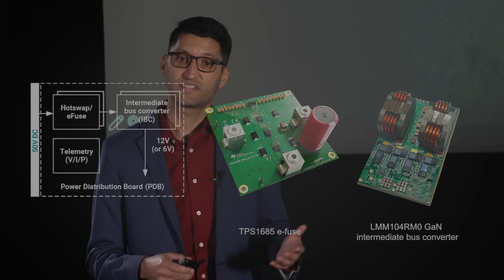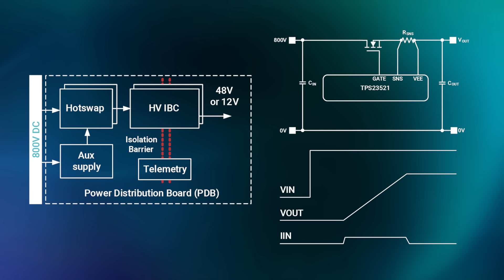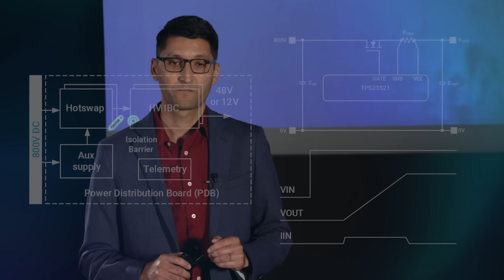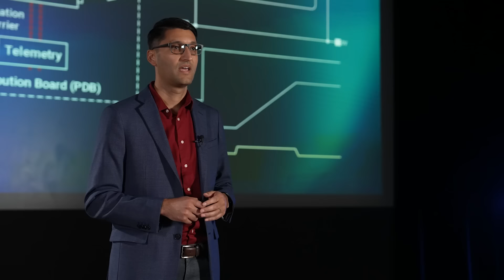With the move to 800 volts, we see 800 volts coming directly to the rack, so the PDB needs to be designed for this high voltage level. You may have hot pluggable inputs that the trays need to be designed for, ensuring that inrush current is limited and smoothly pre-charging the bus capacitance. That's where the hot swap circuit is used to address that challenge and charge those input capacitors of the IBC.